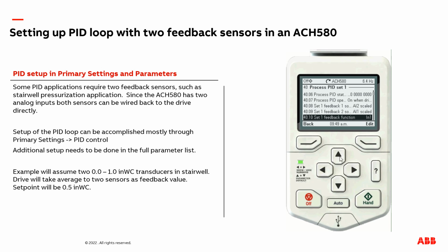The next setting is which feedback sensor are we following. By default, the PID loop only follows one of the sensors, but we're going to select the average. We want to take the average of the signal coming into AI1 and AI2. Now, in your setup, there is a good chance you may select, for example, the min or max setting. This means the drive will look at both analog inputs and it will say whichever one is the minimum, that's my feedback source, or whichever feedback source has a higher value, that is my feedback source. But like I said, we're going to select average. We're going to take the two sensors and average them together.